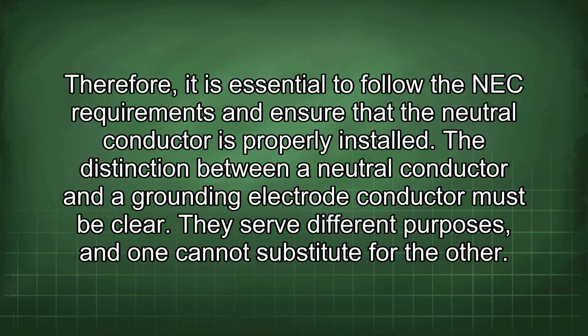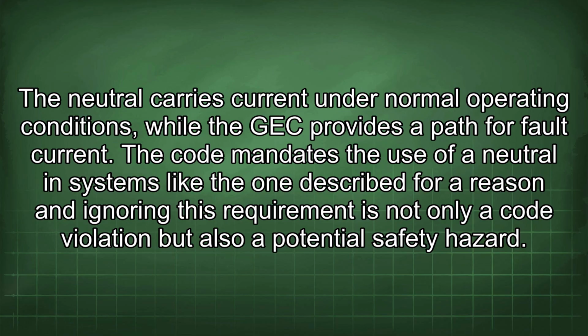The distinction between a neutral conductor and a grounding electrode conductor must be clear. They serve different purposes, and one cannot substitute for the other. The neutral carries current under normal operating conditions, while the GEC provides a path for fault current. The code mandates the use of a neutral in systems like the one described for a reason, and ignoring this requirement is not only a code violation but also a potential safety hazard.